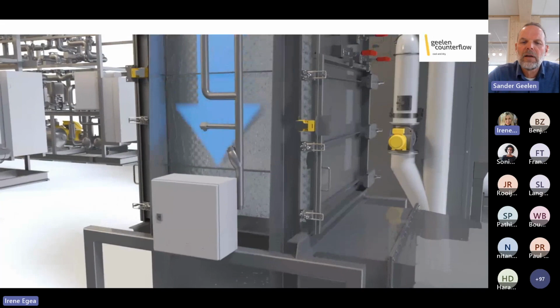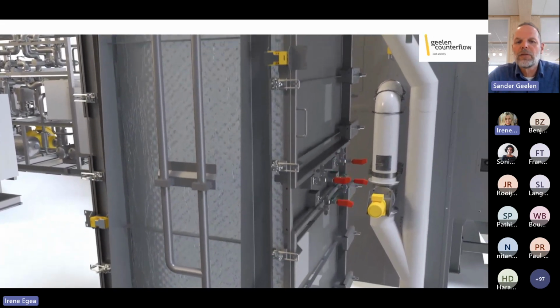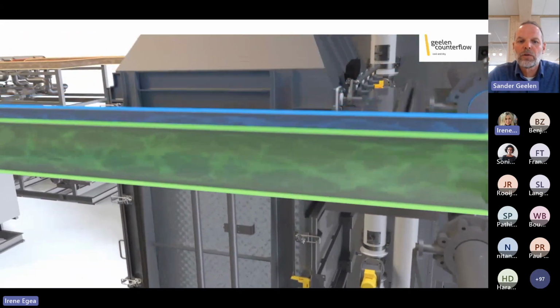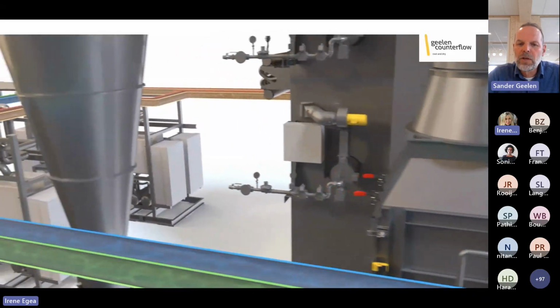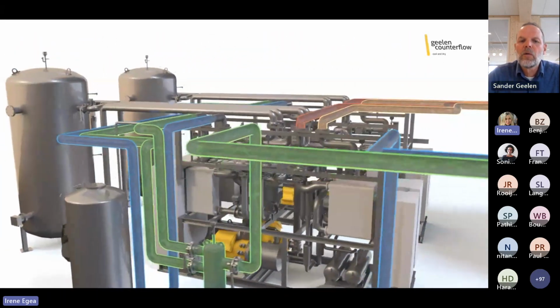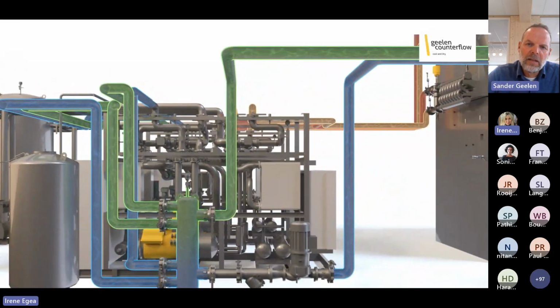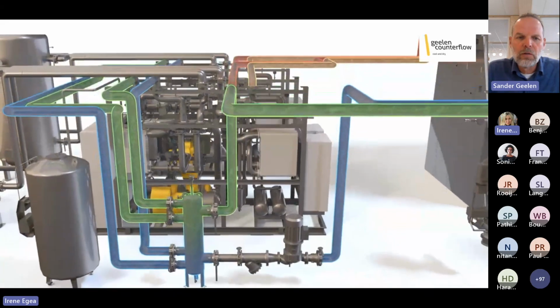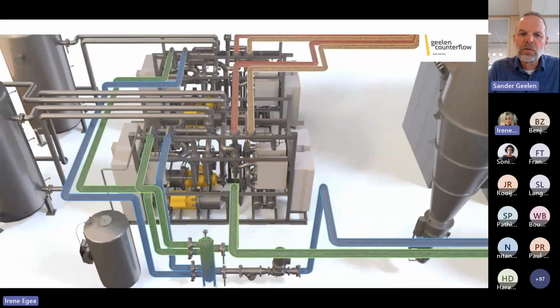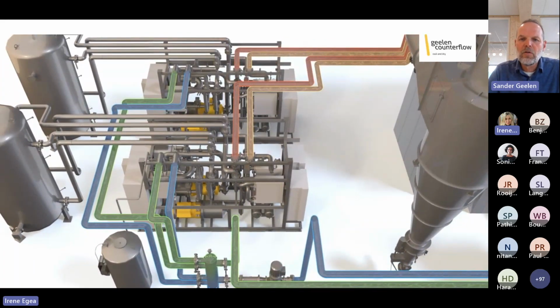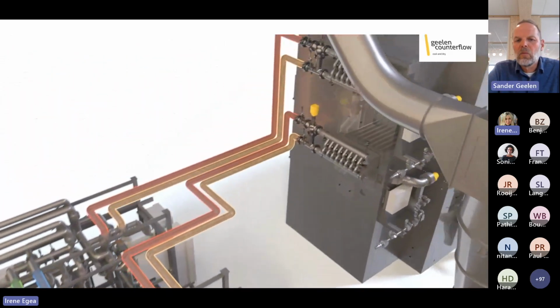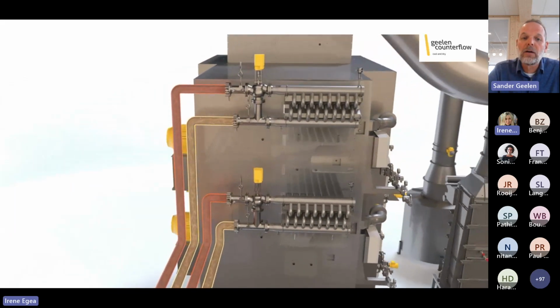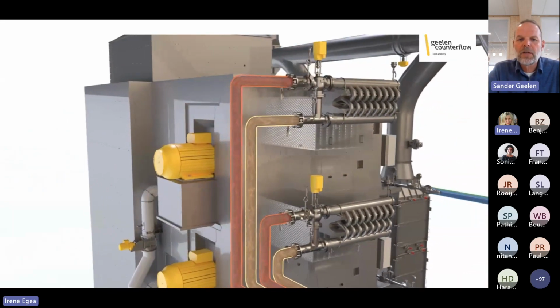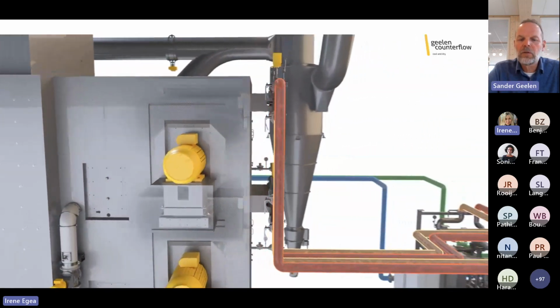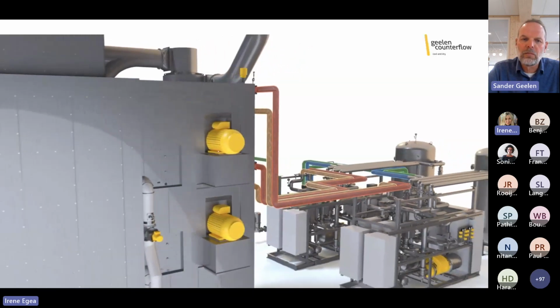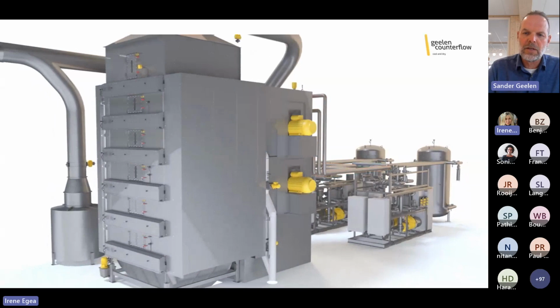There are plate heat exchangers in there, and we call it the counterflow recovery unit because the air is moving top down, and the cold water, the relatively cold water coming from the heat pump, is moving in the opposite direction. So we're using the cold side of the heat pump to trigger the condensation, which allows us to recover the latent energy. And then the heat, which is in this case simulated in the green flow, is moving to two heat pumps and then being boosted to two different temperature levels. And those temperature levels are then moving into the dryer, where we have what we call a secondary heat exchanger, because this is where the dryer now picks up the heat from the heat pumps and converts that into hot air. And again, we do that with plate heat exchangers to minimize the pollution, or to clean up the pollution as easily as possible.